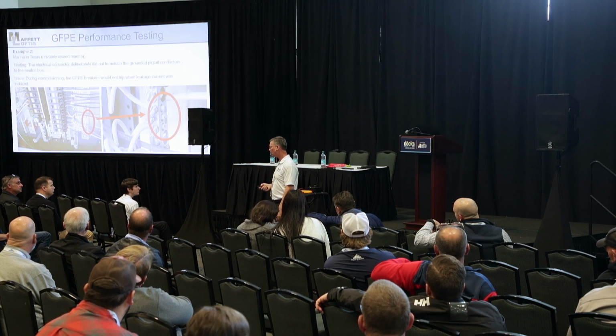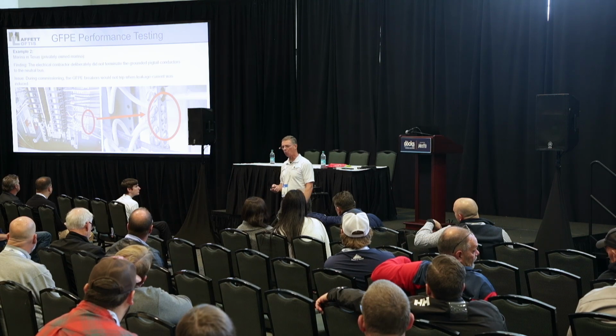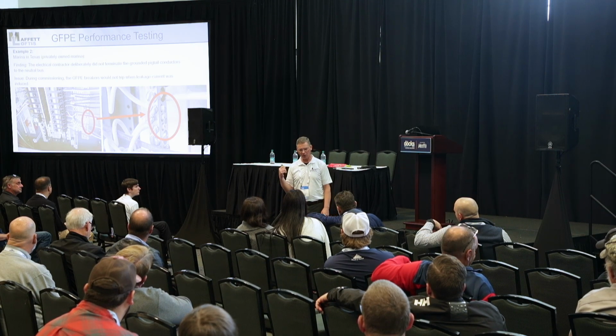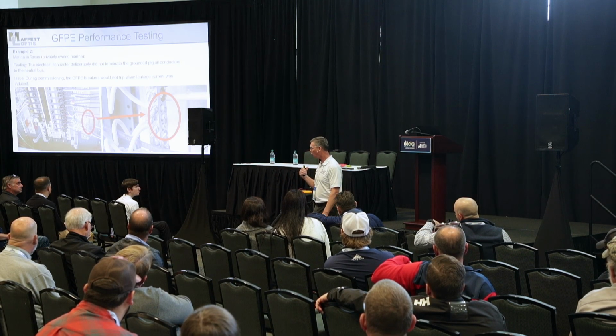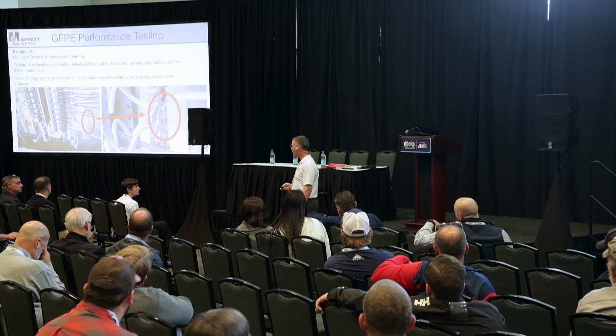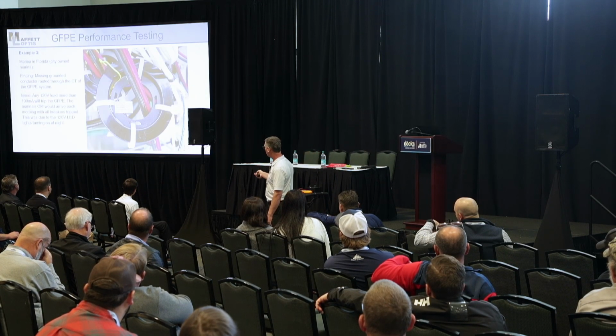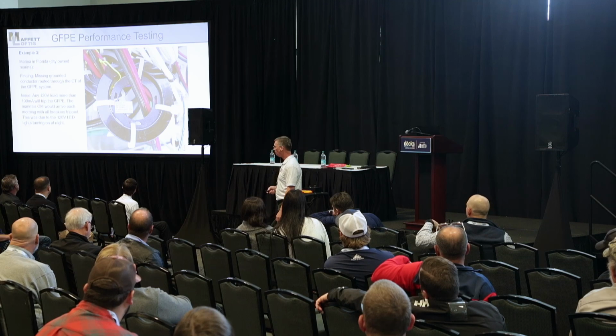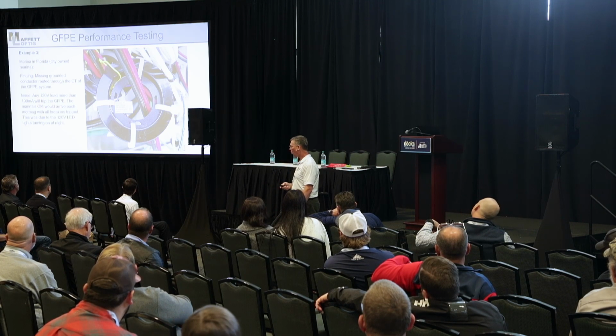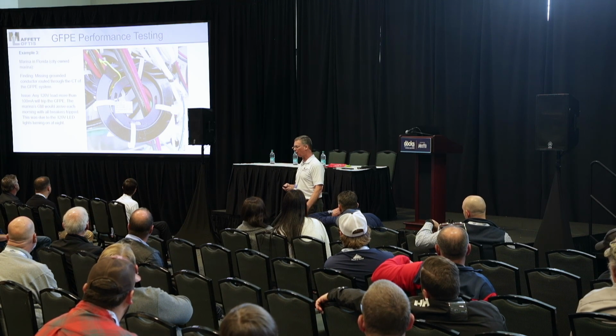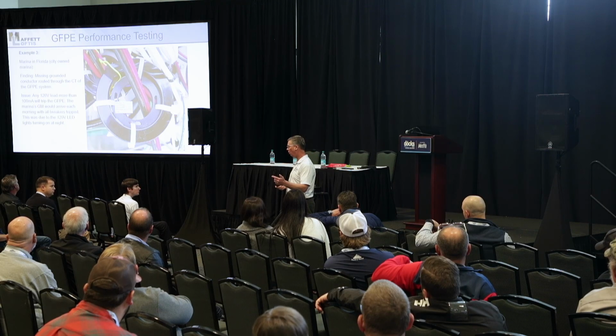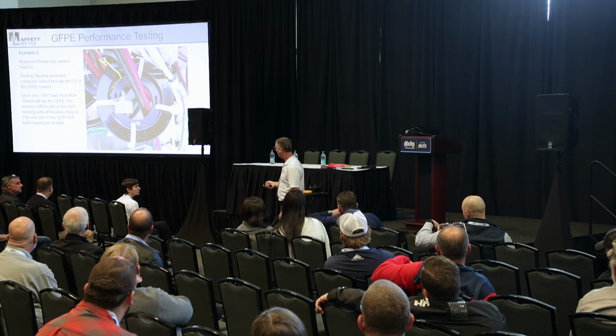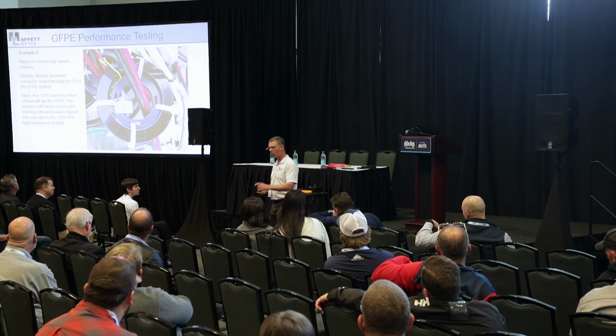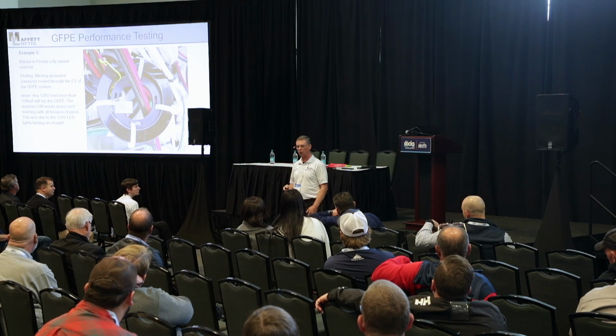The inspector did not see this because it's buried. But when I do the performance testing, I find things like that because it doesn't work correctly. So that's the reason why we're doing performance testing. Here's one with the neutral not in the CT. Okay, that did not work well because every night it'd trip because the photocell on the lights would come on, put neutral currents on the neutral wire, which was outside, and it'd trip. And every morning the contractor would have to come back in and turn the breakers on.